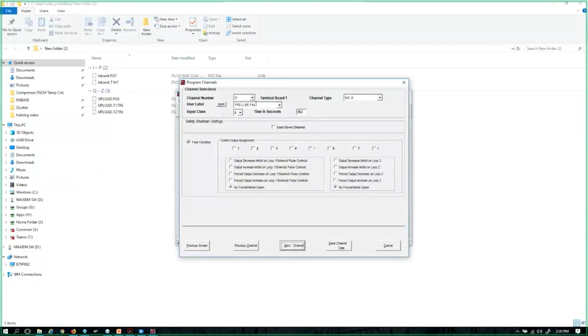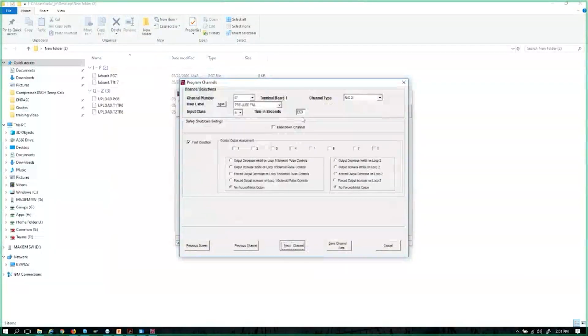but I'm not disconnecting that compressor oil pressure or pre-lube circuit until I hit 150 RPM. Even while the engine's pre-lubing, the compressor will continue to pre-lube until I hit 150 RPM. I know it gets a little confusing. So with a 60-second timer here, if I don't meet that pressure permissive, I will go into a fault about the same time I'm starting to try to send a signal over to the engine to start its startup sequencing.